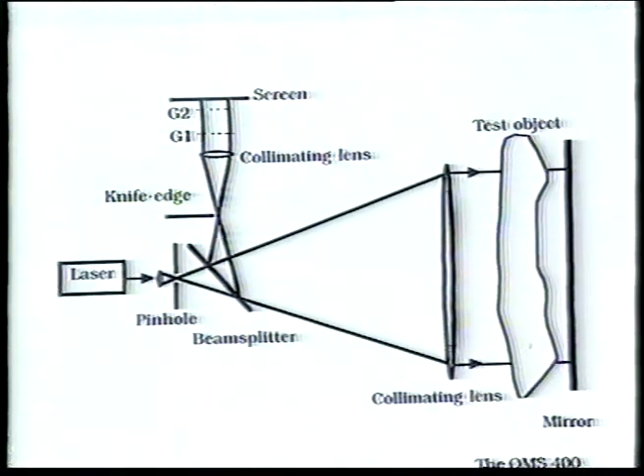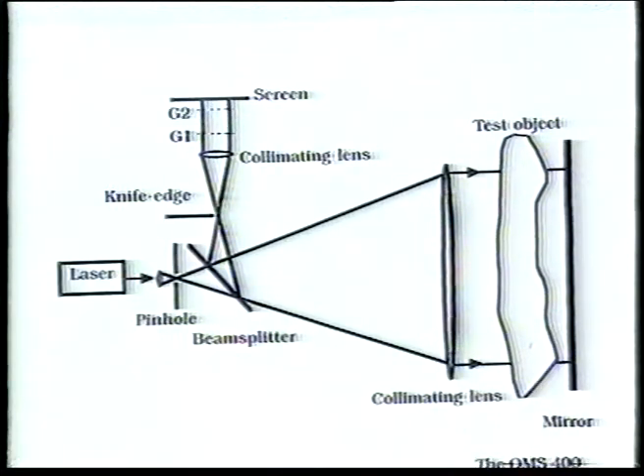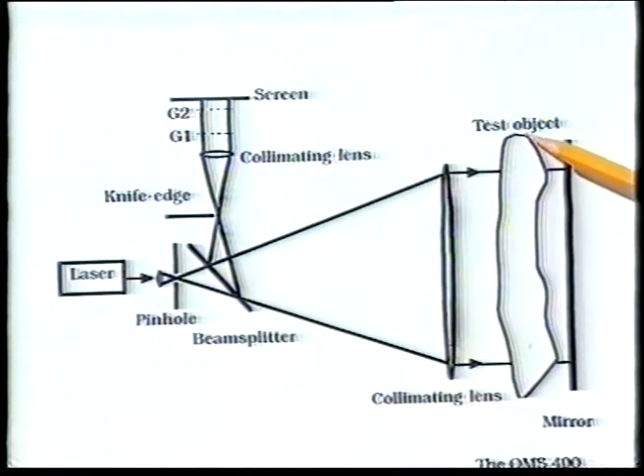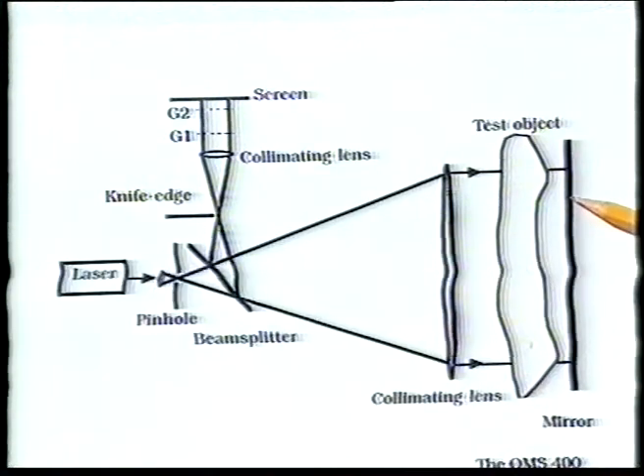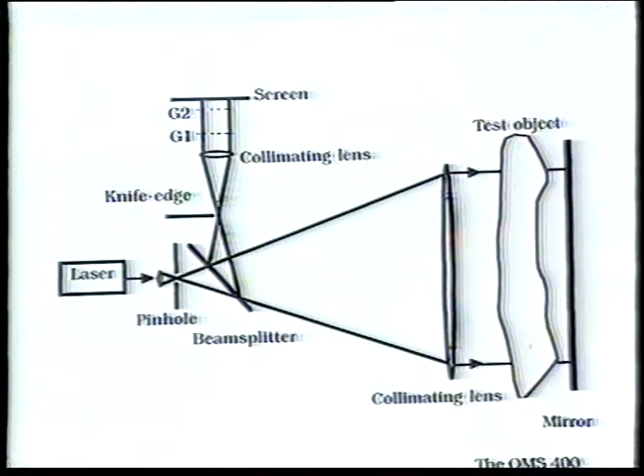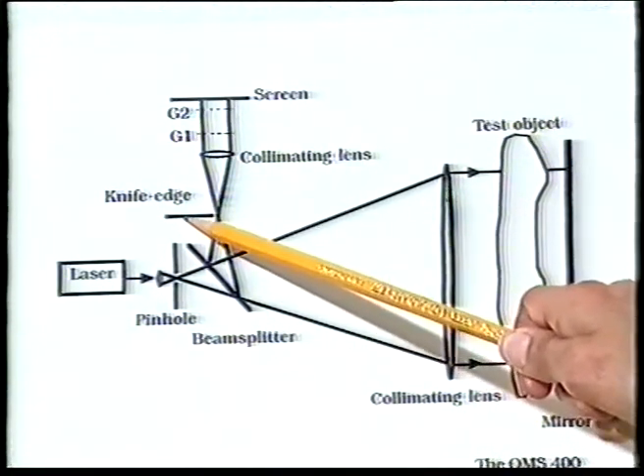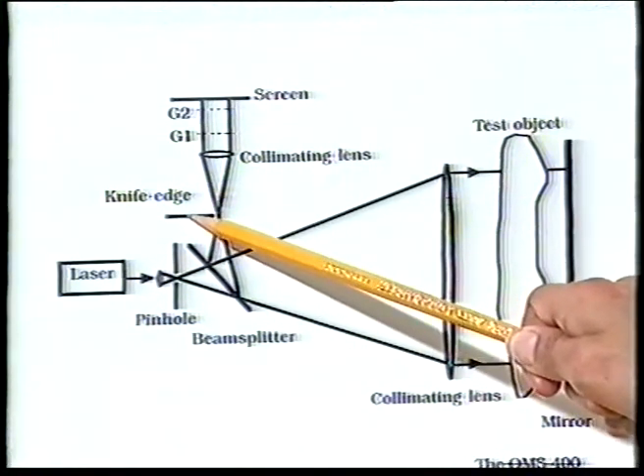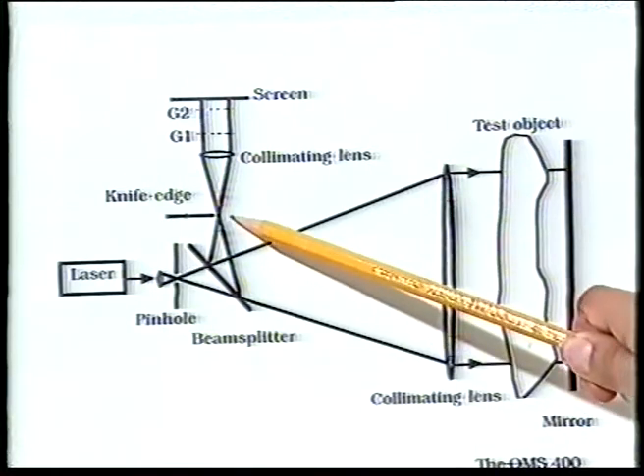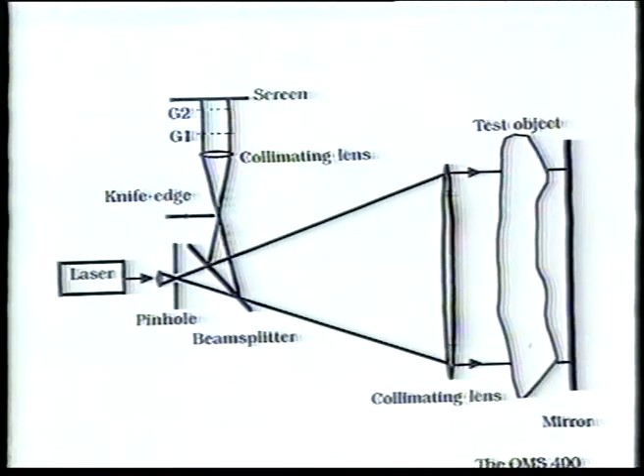Besides Moiré deflectometry, the OMS 400 has two additional modes of operation. FISO option: with the addition of a reference plate parallel to a flat mirror, the instrument can work exactly as a modified FISO interferometer. Schlieren option: a knife-edge spatial filter at the focal plane of the recollimated beam allows the instrument to work as a Schlieren device.